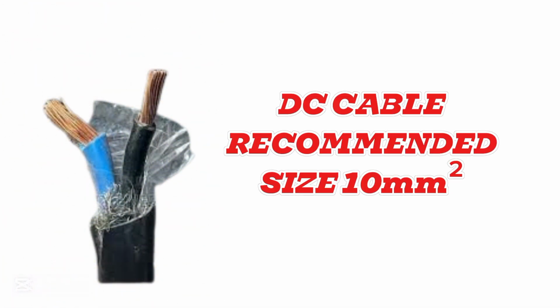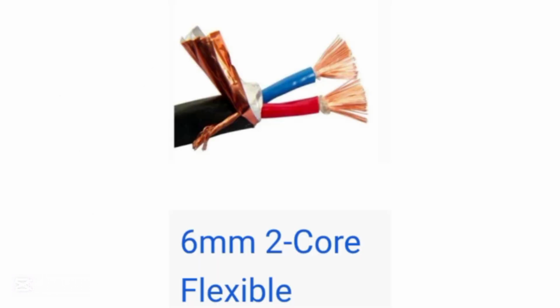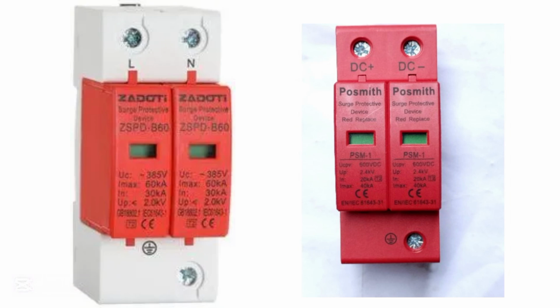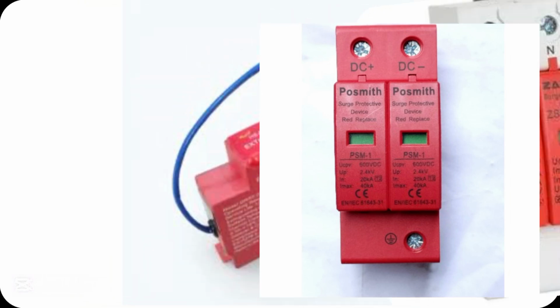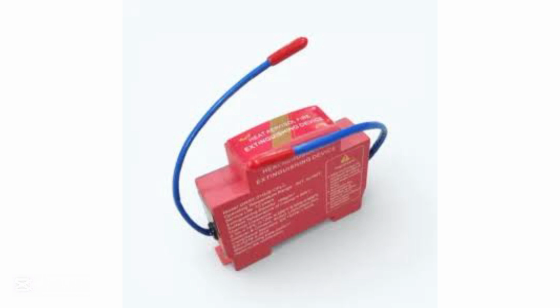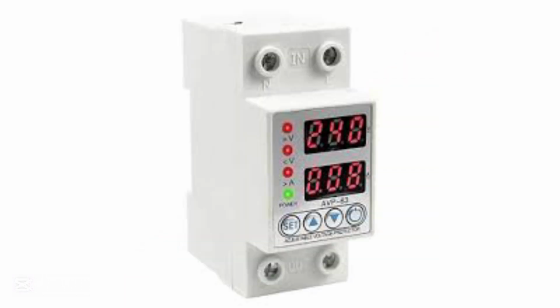Now, for the DC cable, it is recommended you use 10 mm cable, but if 10 mm is not available, 6 mm is the least you can use. Since you're working on a high voltage system, the currents are usually low, and if the distance is not far, it means that there will be no voltage drop. So 10 mm is recommended, but 6 mm can as well serve. We bought two SPDs, AC SPD and DC SPD. We bought the new breaker, fire extinguisher, earth rod, an AVR, and then a good PV box.